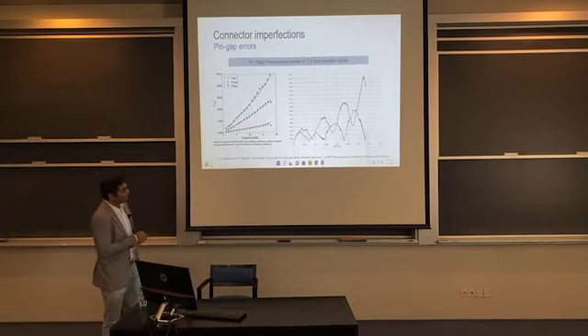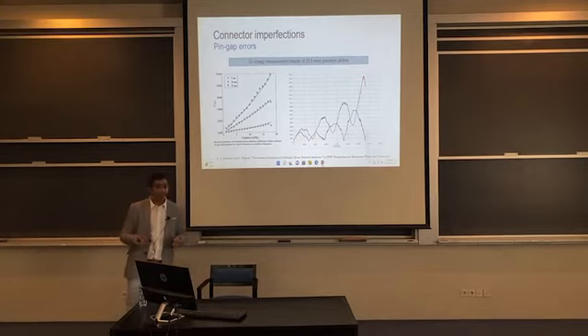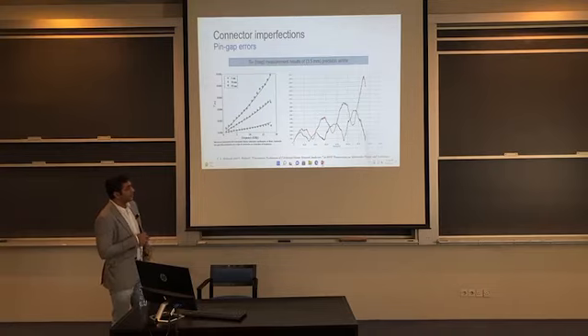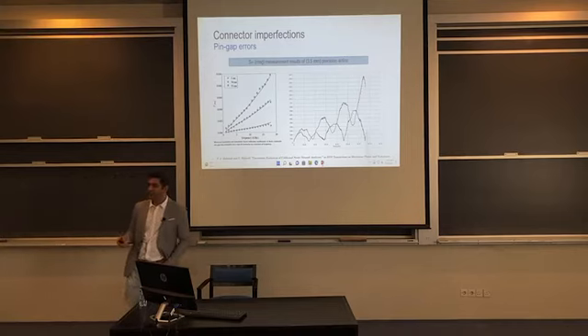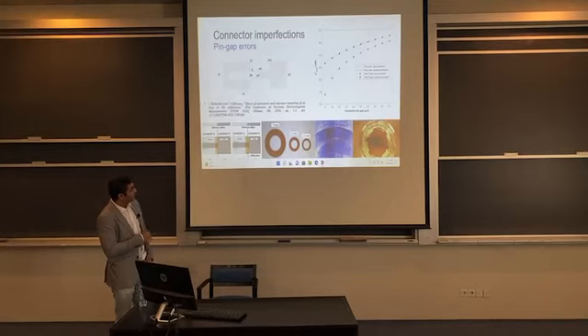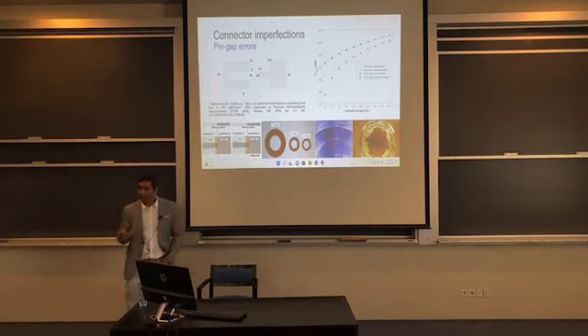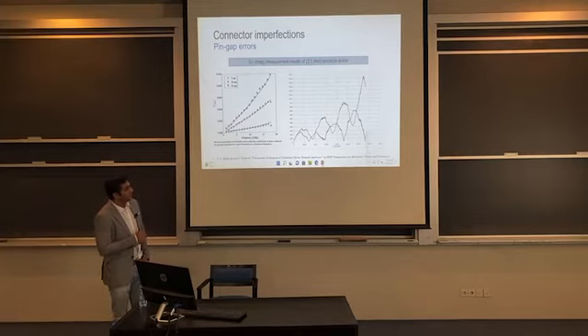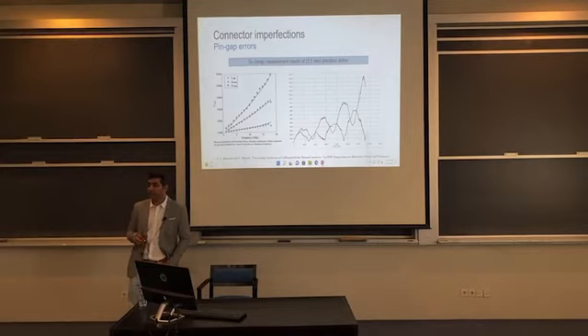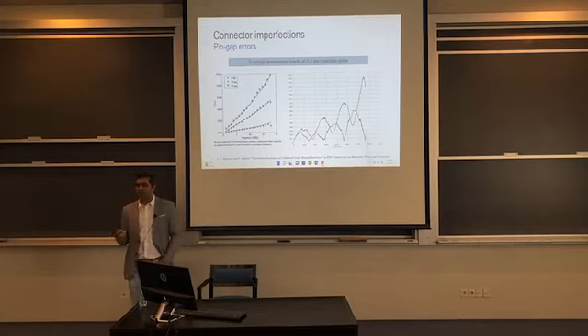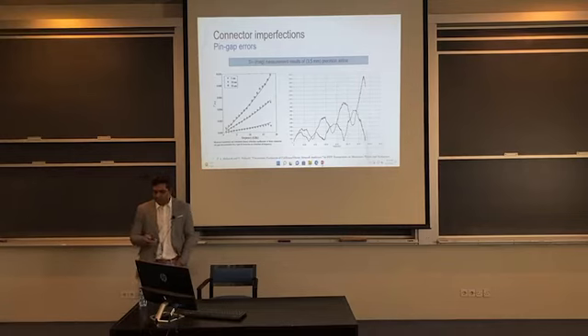Here you can see a reflection measurement of a mechanical precision transmission line. In one of the measurements, and this is the result coming forward from the same transmission line, the only thing that we did is that we positioned the center conductor in one of them using such offset discs, which basically are there to de-embed the pin gap effect that we get from such imperfect connectors. And if you don't use them, you can see the difference between the two measurements is actually much bigger than the accuracy that we claim. So it makes sense to actually even align these transmission lines with about 10 to 20 micron offsets. Even those dimensions matter and are actually critical.